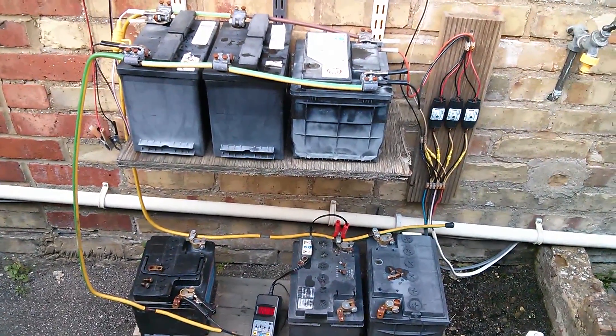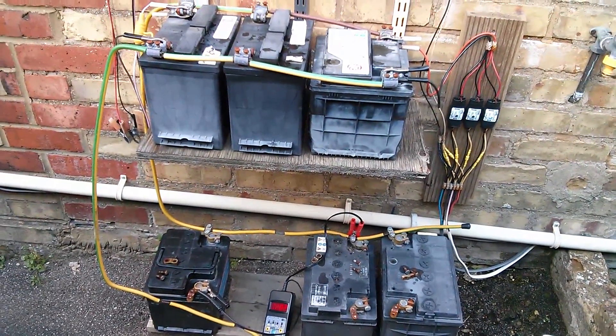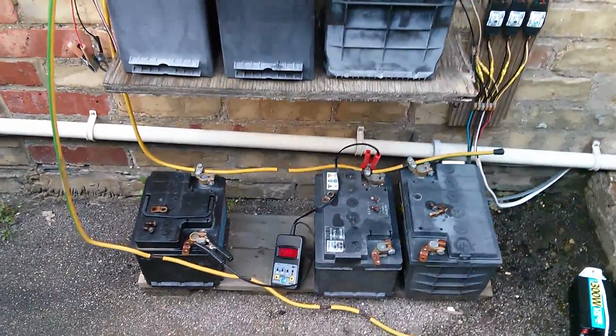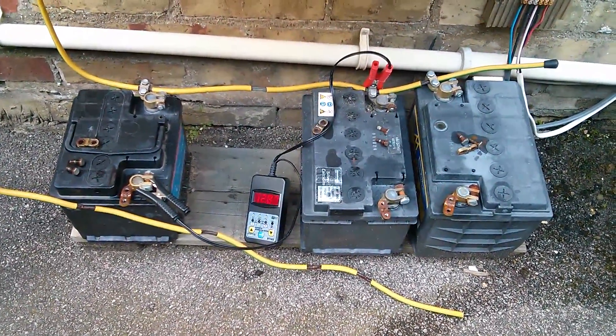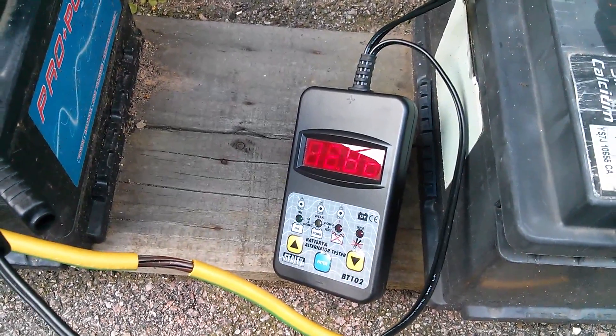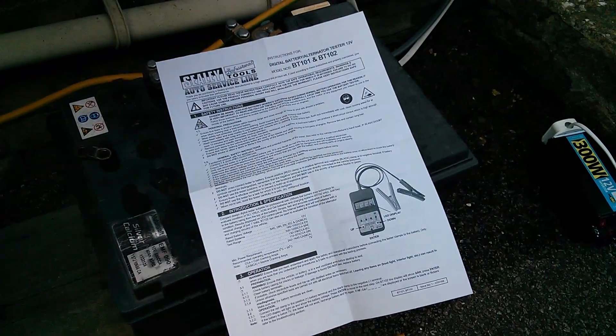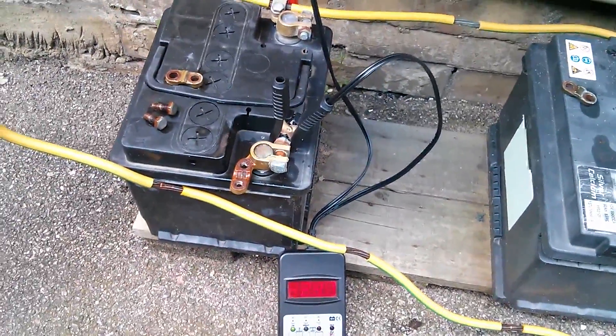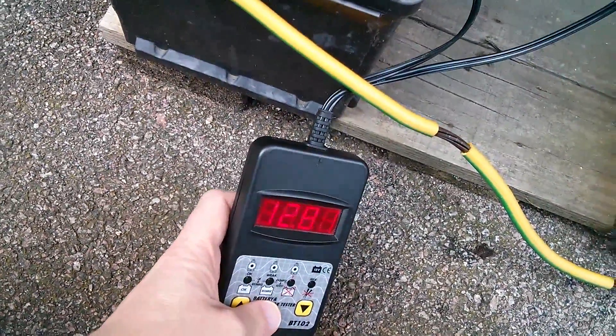Good afternoon. It's a reasonably nice day today, so I thought I'd test some of these batteries on my solar power station. I'm going to test the bottom three because it's fairly easy to disconnect those. I've removed the negative cable from those so they're all isolated, and I've connected up the battery tester — it's the Sealey BT102. I've just been reading up on how it works, and I think I've got the hang of it. I've hooked it up to the left-hand battery to test that one first.